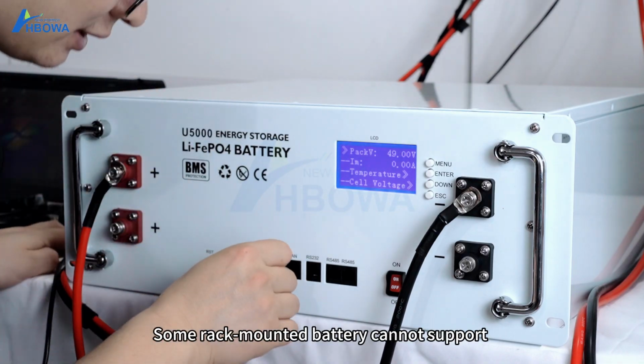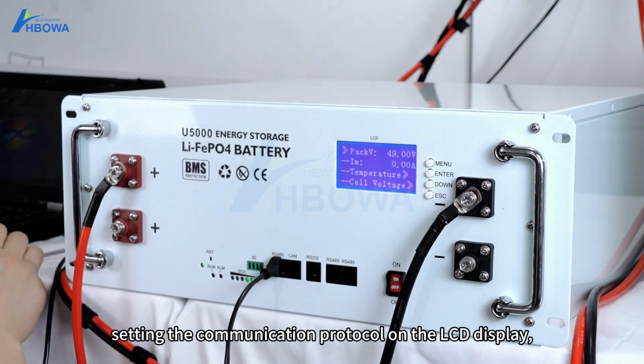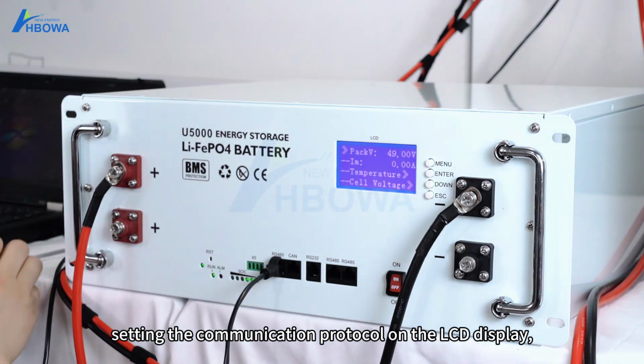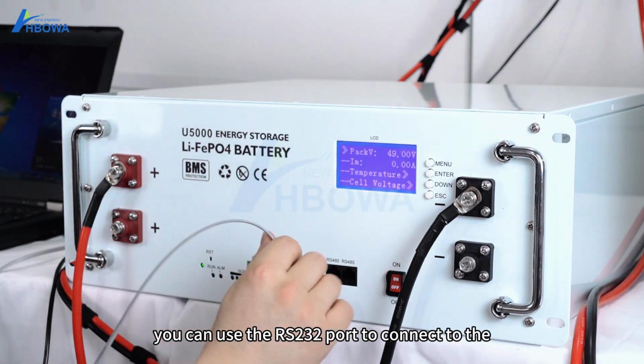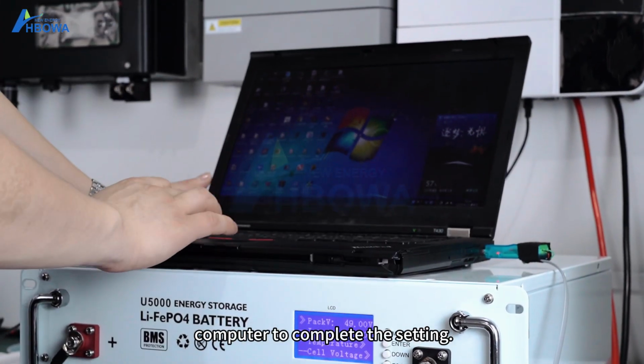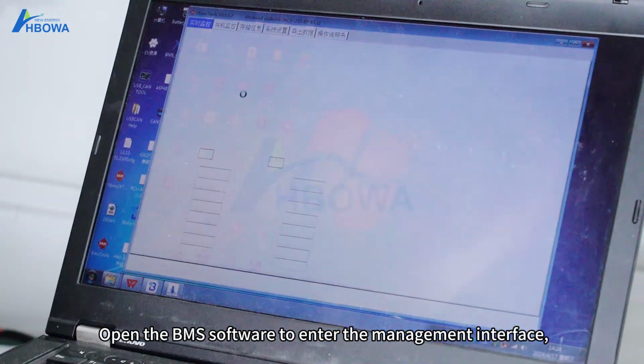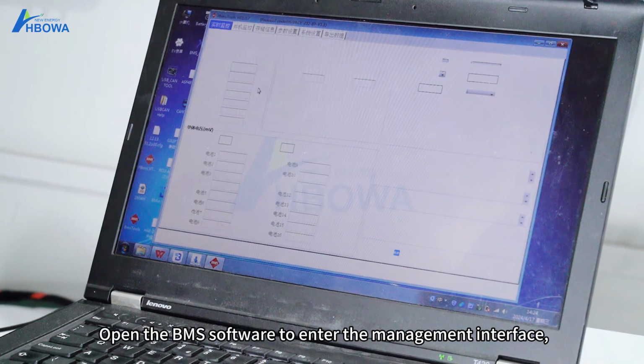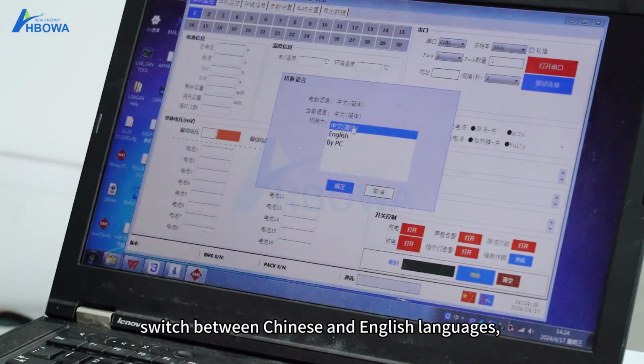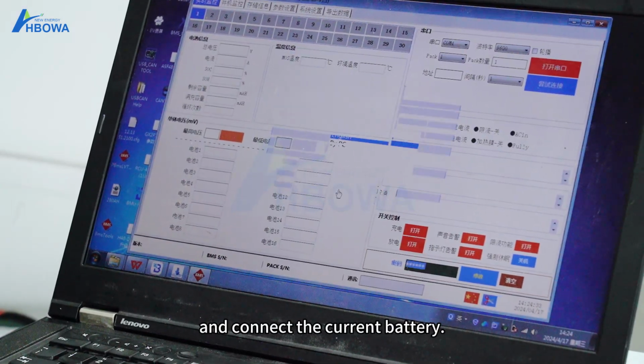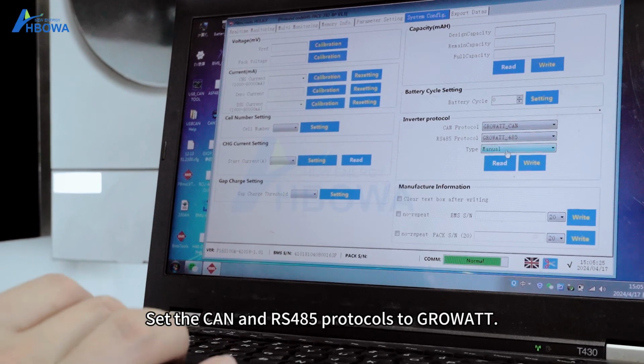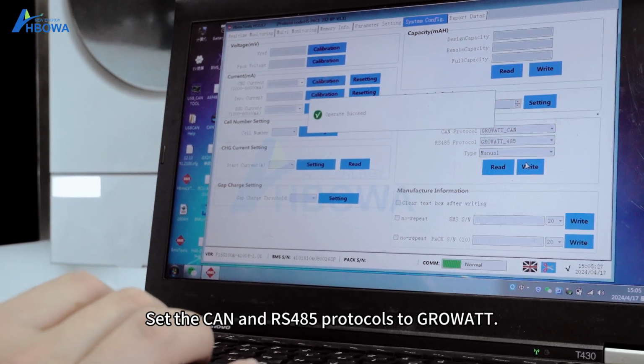Some rack-mounted batteries cannot support setting the communication protocol on the LCD display. You can use the RS-232 port to connect to the computer to complete the setting. Open the BMS software to enter the management interface, switch between Chinese and English languages, and connect the current battery. Set the CAN and RS-485 protocols to Growatt.